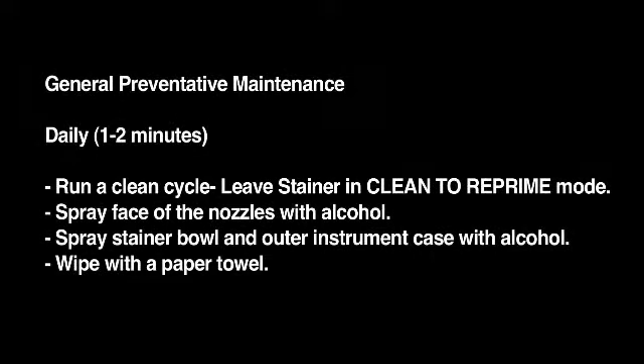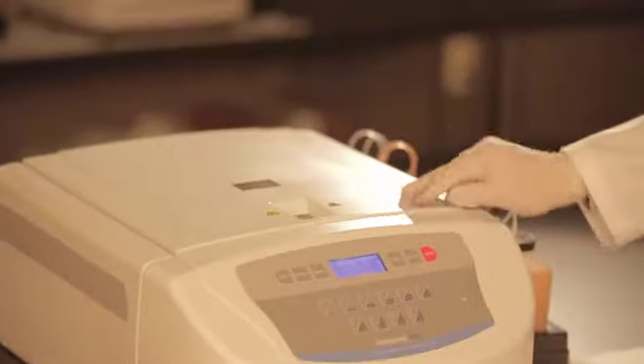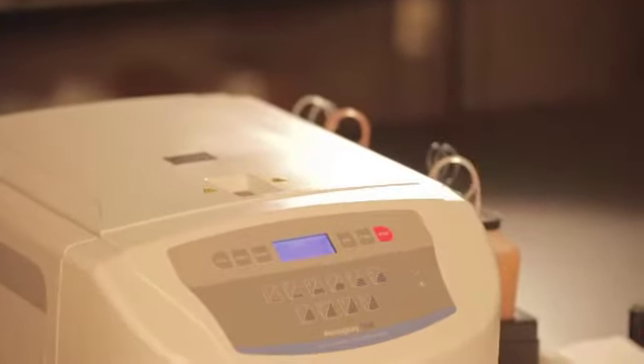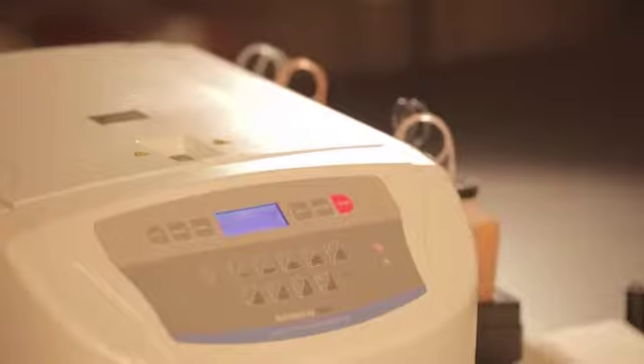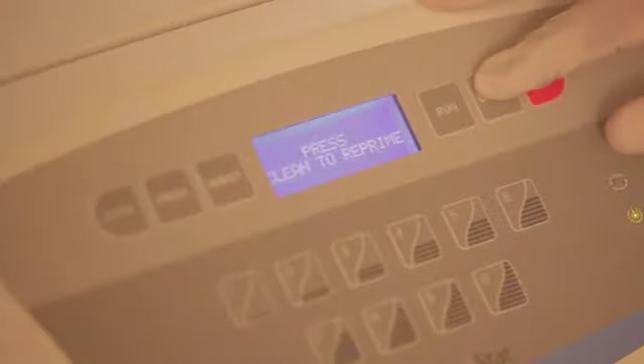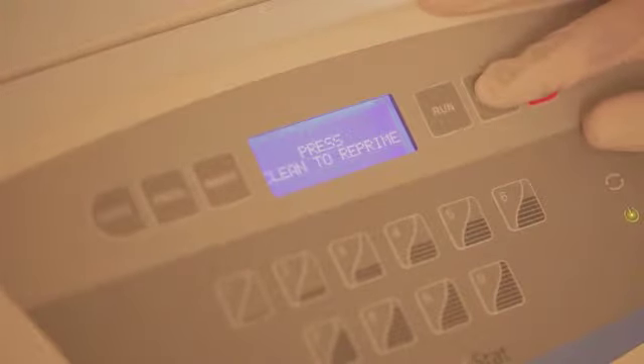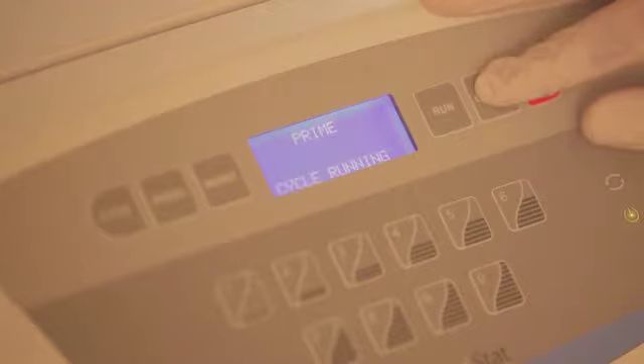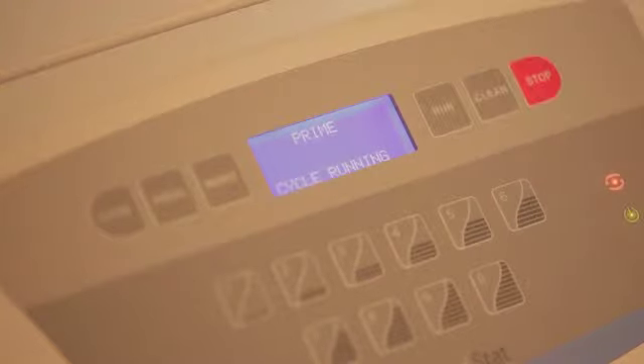The daily preventive maintenance is quick and easy. Run a clean cycle at the end of each 8-hour working shift, or if the stainer is going to sit idle without use for 4 hours. To perform a clean cycle, press the Clean button. The stainer sprays alcohol through each line. At the end of the clean cycle, Clean to reprime will be displayed on the screen. Leave the stainer in this mode until slides are ready to be stained again, which may be in a few hours or the next day.